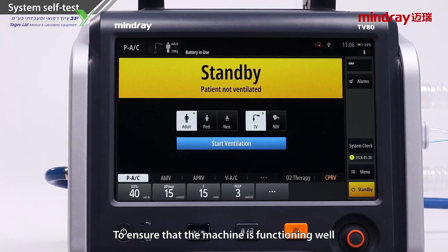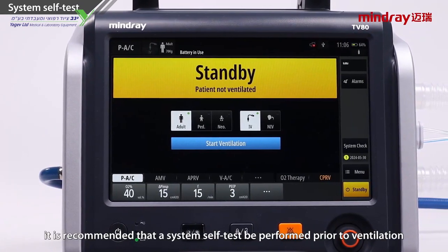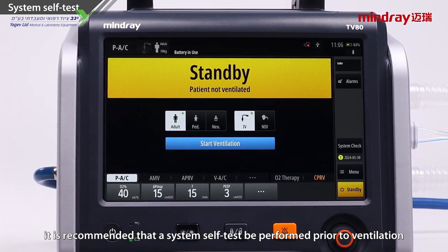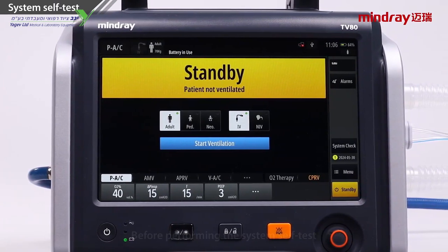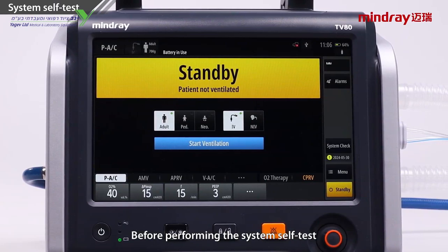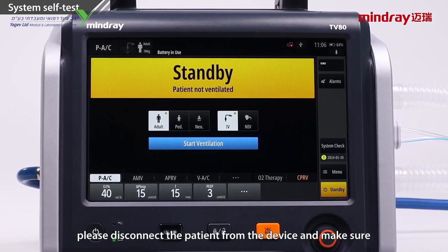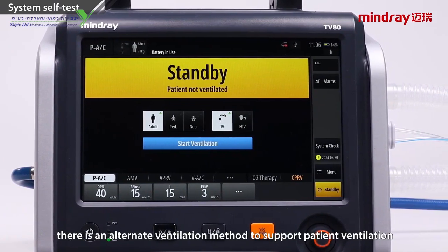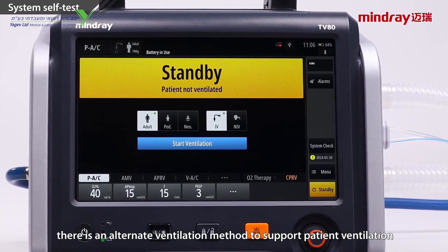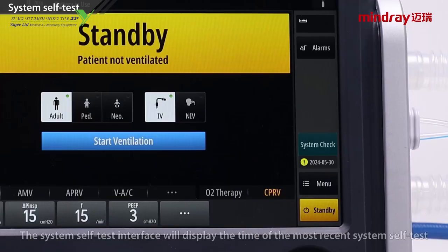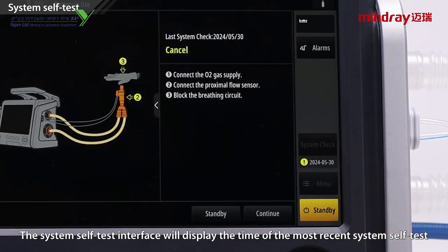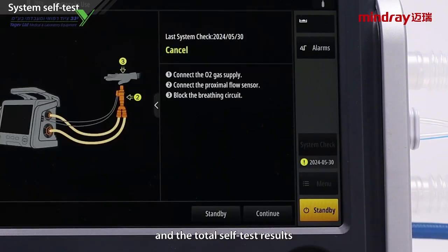To ensure that the machine is functioning well, it is recommended that a system self-test be performed prior to ventilation. Before performing the system self-test, please disconnect the patient from the device and make sure there is an alternate ventilation method to support patient ventilation. The system self-test interface will display the time of the most recent system self-test and total self-test results.